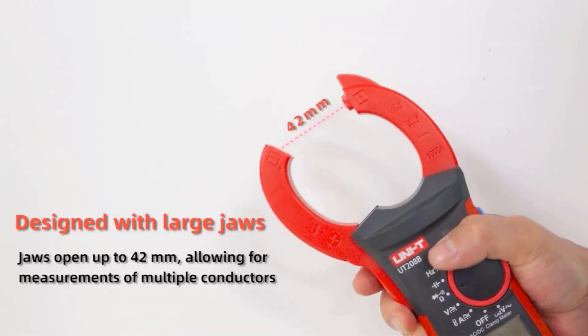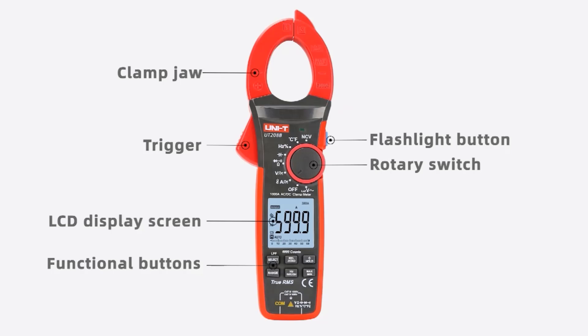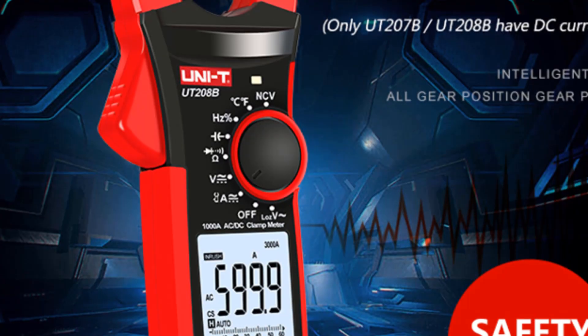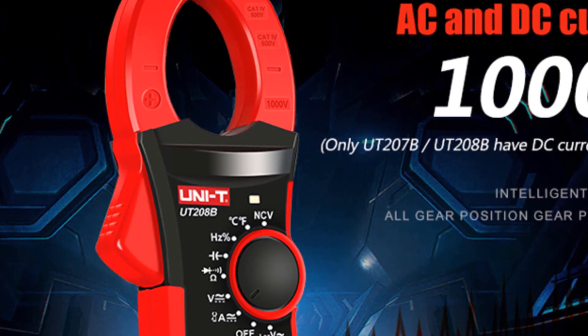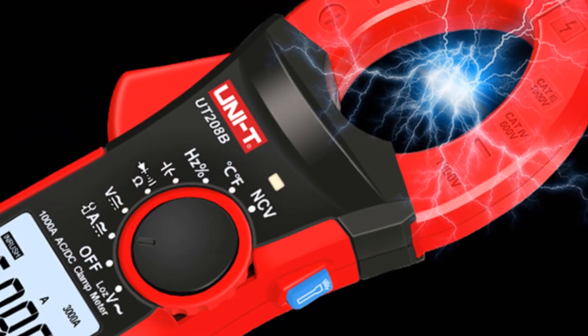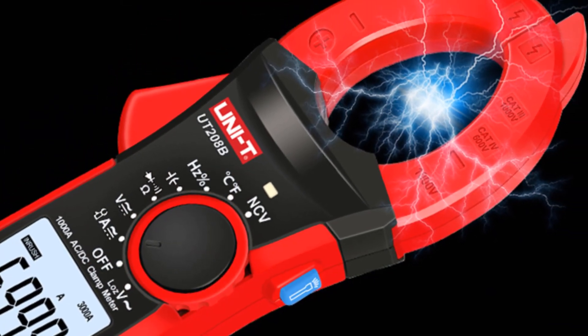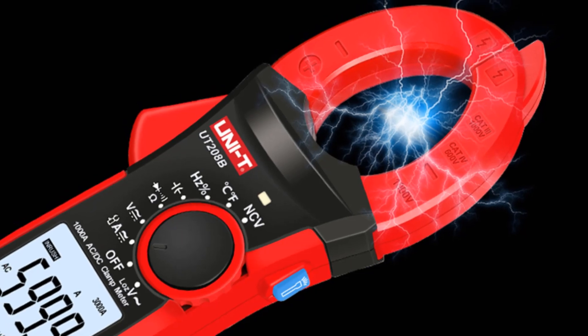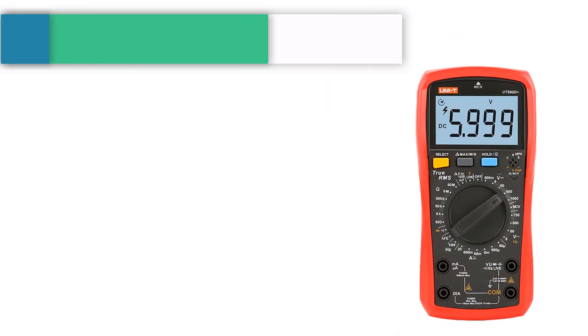The UT206B, UT207B, and UT208B come with LoZ mode for eliminating ghost voltage, LPFACV function for measuring inverter and VFD voltage, and inrush current mode for capturing transient current. The UT206B and UT208B also feature high-precision temperature measurement with 0.1°C resolution, and can be equipped with a flexible current probe to extend the AC current measurement range up to 3,000A.